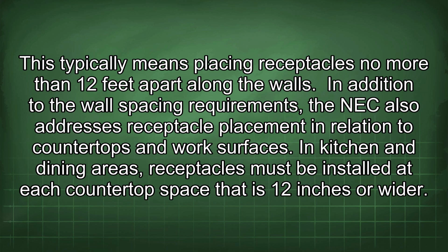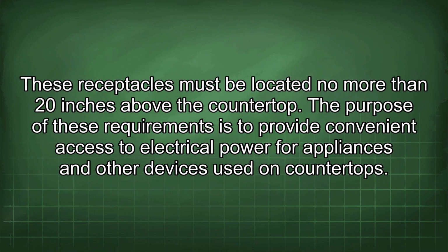In addition to the wall spacing requirements, the NEC also addresses receptacle placement in relation to countertops and work surfaces. In kitchen and dining areas, receptacles must be installed at each countertop space that is 12 inches or wider. These receptacles must be located no more than 20 inches above the countertop. The purpose of these requirements is to provide convenient access to electrical power for appliances and other devices used on countertops.